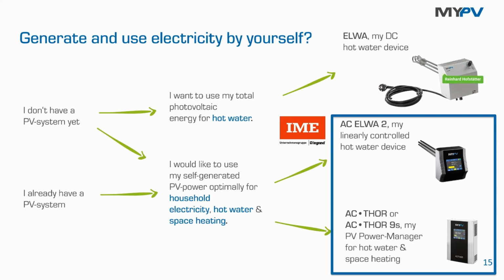Now we want to concentrate on AC products, because there IME comes into the game. There are 2 options. Number 1 is a product named AC ELWA 2. It's a power controller, and the power controller is combined in one product with an immersion heater. So you have an all-in-one solution. The immersion heater, the heating rod, comes together with the power controller for the heating rod. This has an advantage for all projects where the end customer does not yet have an immersion heater in his tank. So it's quite attractive to make an offer with this combined solution.